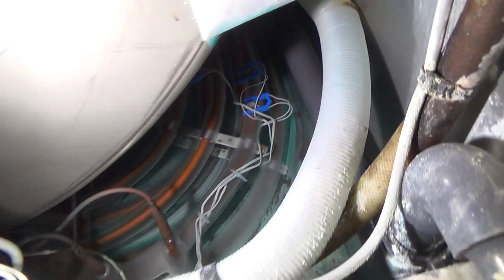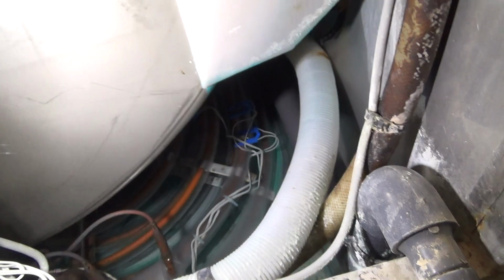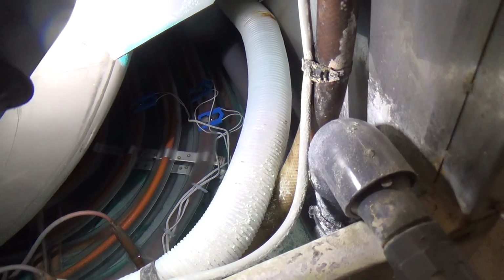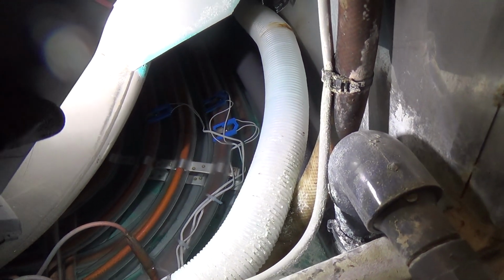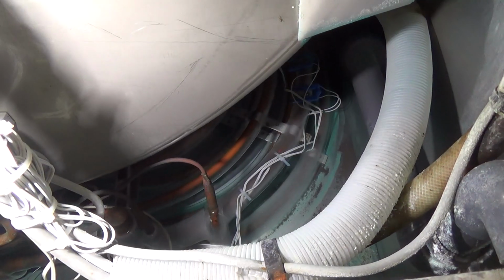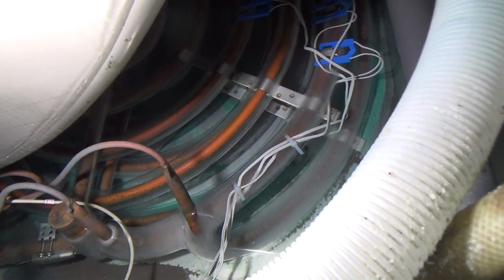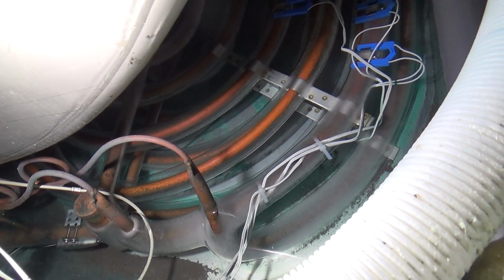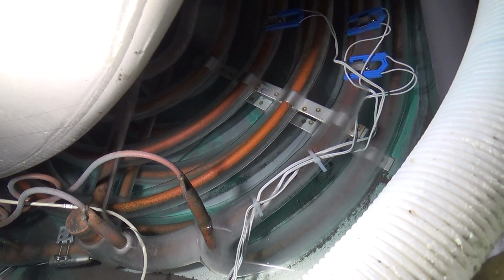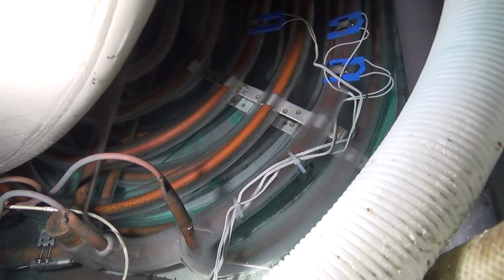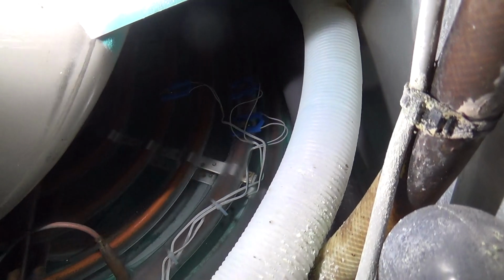And then you've got 2 other ones, which is your plus and minus 50% ice bank probes, and they are set so that if you're not filling the tank, if you're only half filling or below half filling the tank, you can run it on the minus 50, and it'll make less ice. So obviously the more ice it makes, the less efficient it is, because the pipe is doing the cooling, and it's got to cool all the way through to the outer edge of the ice to bring any heat in. So the thicker the ice, the less efficient it is.